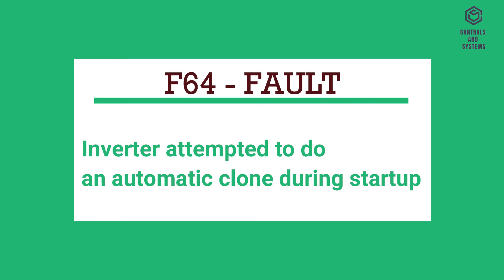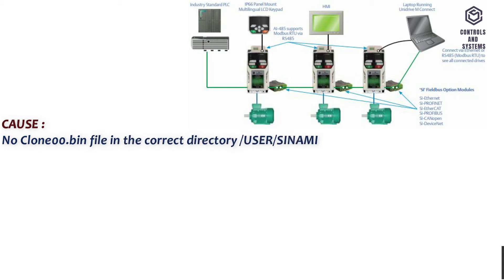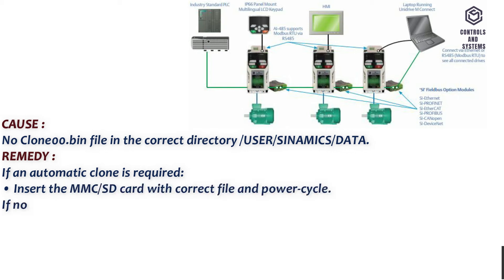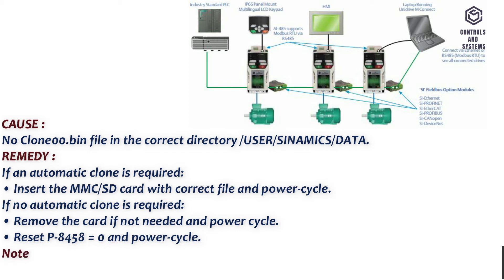F64 Fault: Inverter attempted to do an automatic clone during startup. Cause: No clone .bin file in the correct directory /user/sinamics/data. Remedy: If an automatic clone is required, insert the MMC/SD card with the correct file and power cycle. If no automatic clone is required, remove the card if not needed and power cycle. Reset P8458 equals 0 and power cycle. Note: Fault can only be cleared by a power cycle.